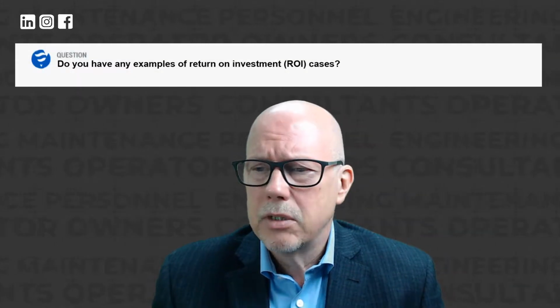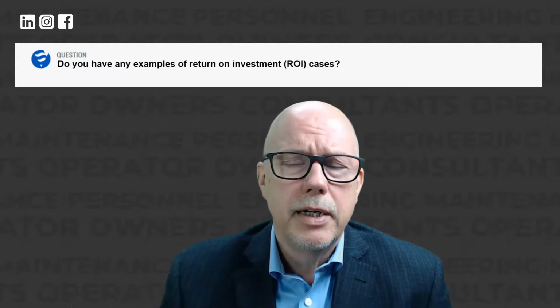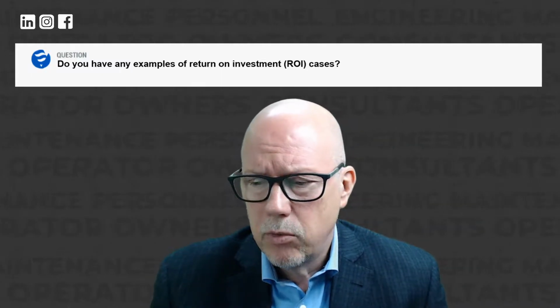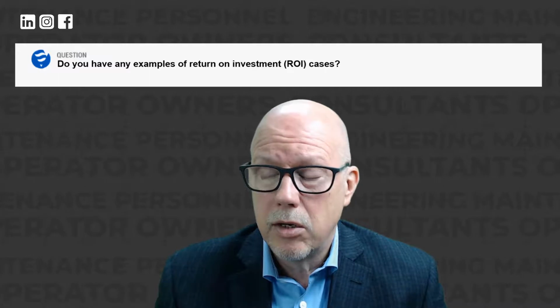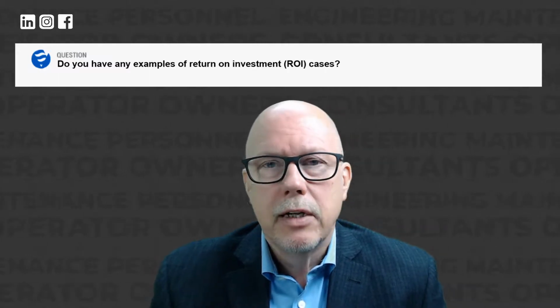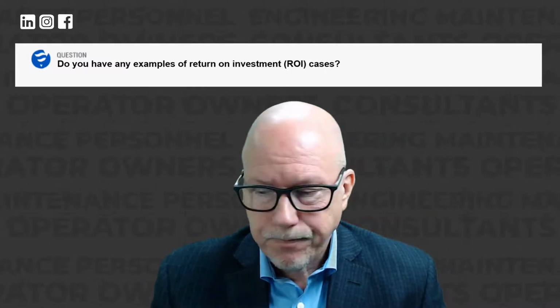One case that comes to mind was in the northwestern United States, where the utility suspected they had some serious rotor rim issues with their vertical hydro generator. They had planned, about 9 months down the road, a major refurbishment, in fact replacing the stator, since it was quite old and they felt it needed to be replaced with a new one.